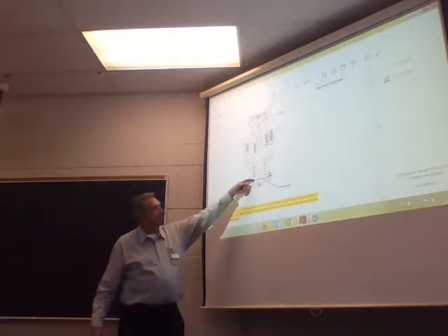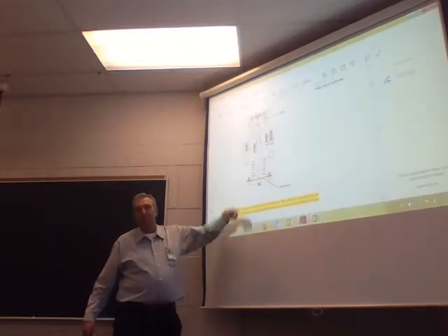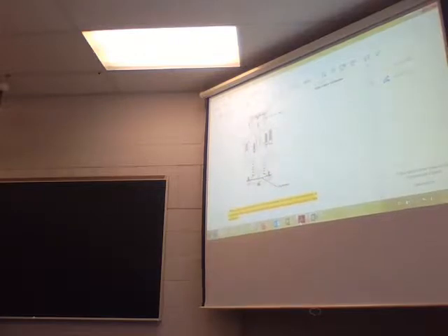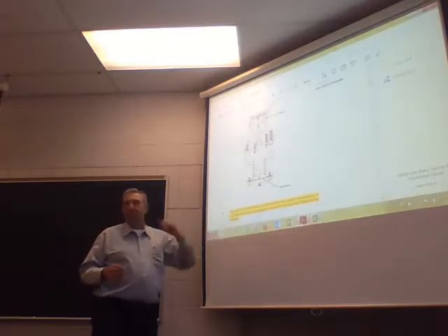And then when the pressure starts to go down, the pressure is relieved on the diaphragm, spring overcomes the diaphragm pressure. Sorry? No, that's how it runs consistently, all the time. The unload, you're talking about an unloader for startup. Understand that it's the same theory, a little bit different. There's actually a solenoid valve on this line that will push pressure in and put it up, but yes. So all the time, these will work.